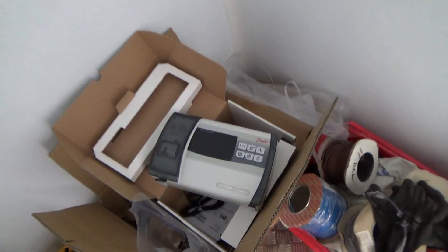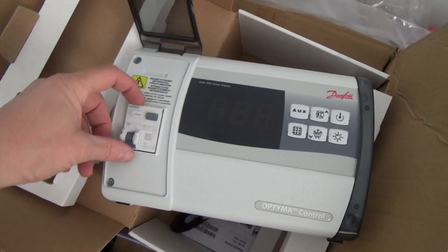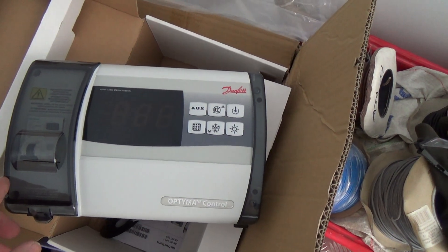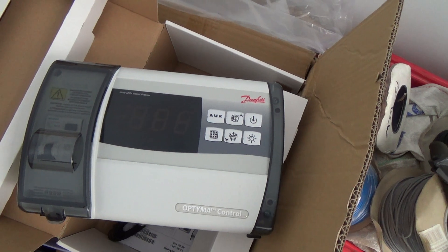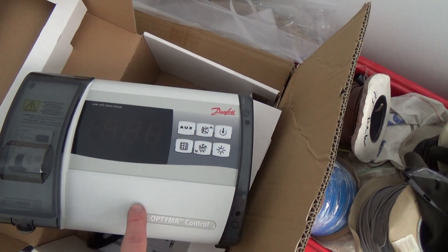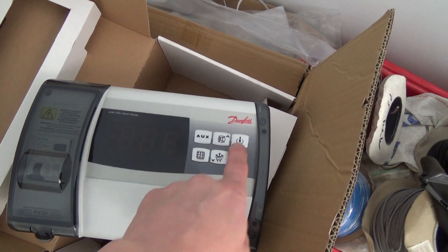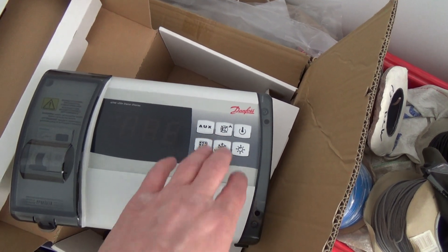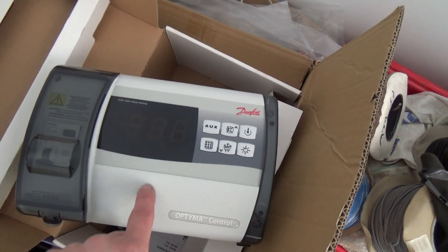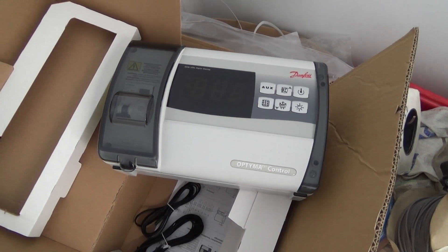And then we've got this Danfoss Optyma controller — it's got a built-in breaker and an earth leakage trip. I've been fitting these for a few years and I've not had any trouble with them at all. The only issue is when you turn them off they still show the temperature display, and I've had a few people who've turned them off to clean the room or something, and then you get a phone call saying the thing's too hot. You have to get them to make sure it's actually on.